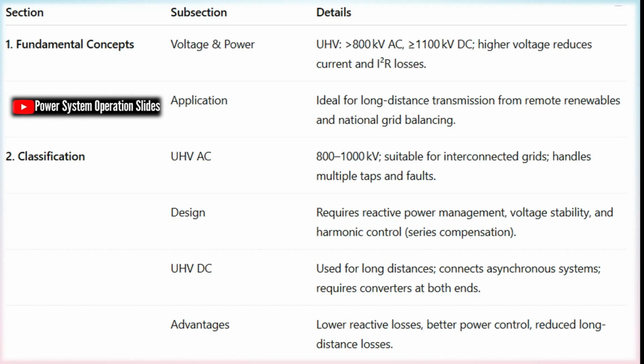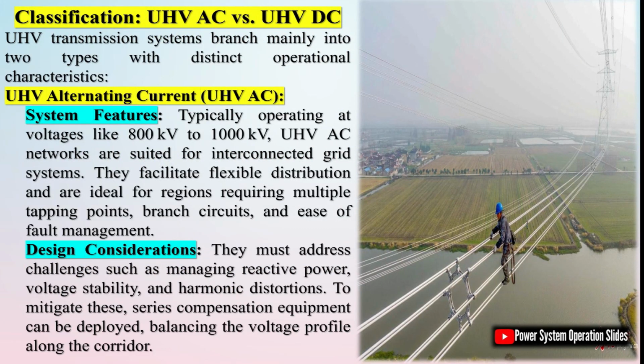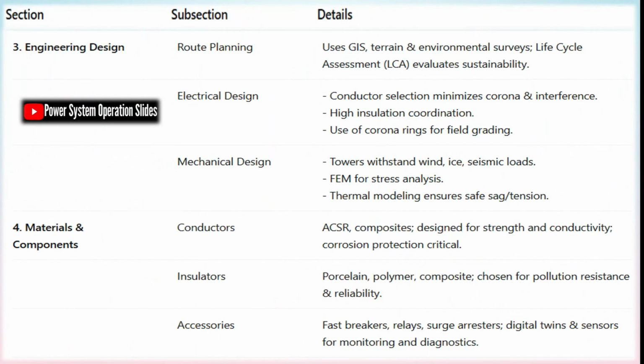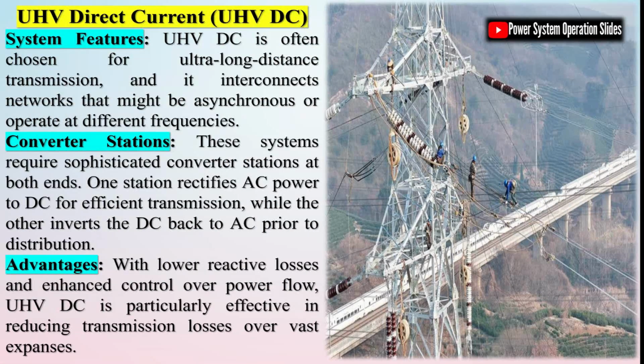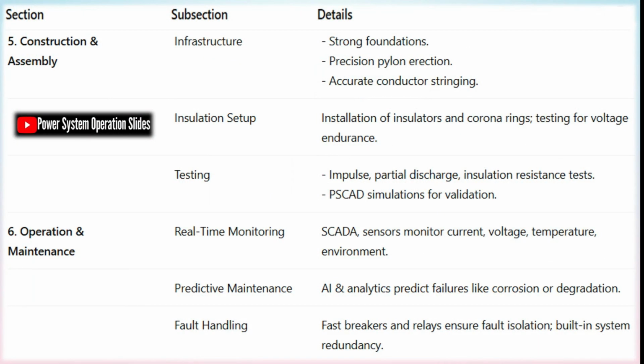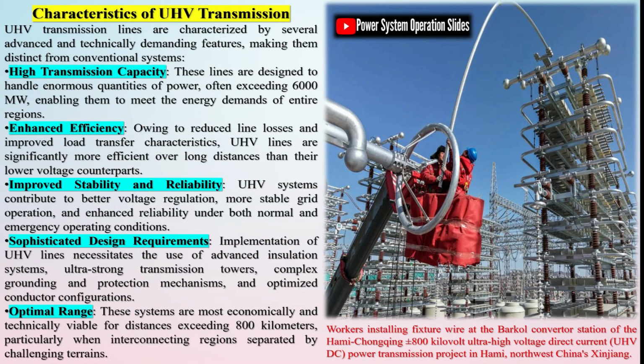UHV transmission systems branch mainly into two types with distinct operational characteristics: UHV alternating current (UHV AC), typically operating at voltages like 800 kV to 1000 kV. UHV AC networks are suited for interconnected grid systems. They facilitate flexible distribution and are ideal for regions requiring multiple tapping points, branch circuits, and ease of fault management. They must address challenges such as managing reactive power, voltage stability, and harmonic distortions. To mitigate these, series compensation equipment can be deployed, balancing the voltage profile along the corridor.